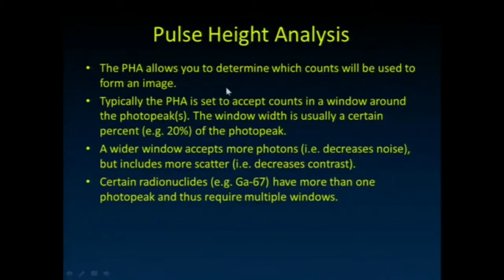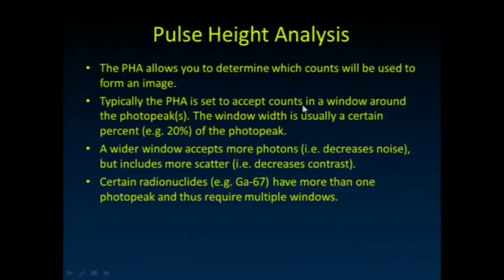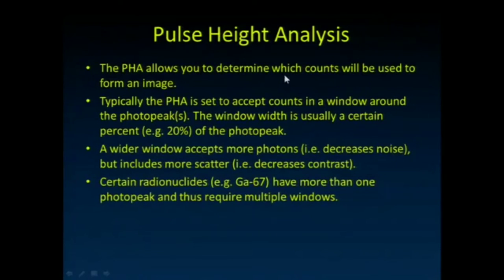We perform pulse height analysis — the total amount of light corresponds to the height of the pulse, allowing us to discern the energy of the detected gamma ray. We typically accept events that fall within a certain window around the peak, called the photo peak window, typically about 20% wide. For 140 keV technetium, we accept from about 126 keV up to about 154 keV. Any pulses whose estimated energy falls in that range are accepted to make our image.